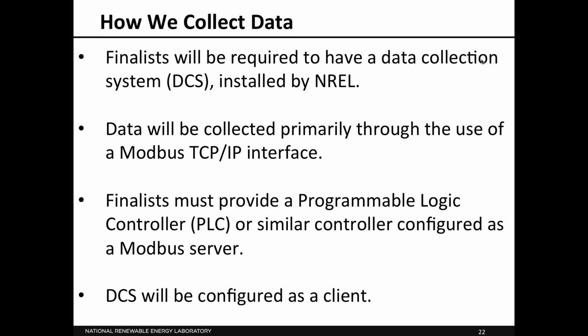And the DCS that NREL will provide will be configured as a Modbus client, and we'll ask the server about every 30 seconds for any system data. It's important to note that we're not requiring an additional PLC. So whatever main PLC that you have to control your system, that's adequate, as long as it can speak Modbus over the TCP/IP protocol, that will be fine. So you don't need an additional PLC just for data collection.